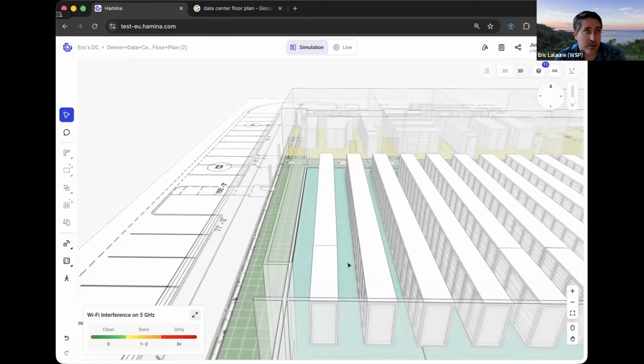It's mostly polycarbonate, so maybe not a huge attenuation on Wi-Fi signal. However, you will have structural elements, essentially made of unistrut or equivalent aluminum or steel members, that maintain those polycarbonate panels, just to block all the possible ways cold air could flow directly into the hot aisle, because you want the cold air to go through the servers, not around it. So you'd essentially seal that as much as possible.